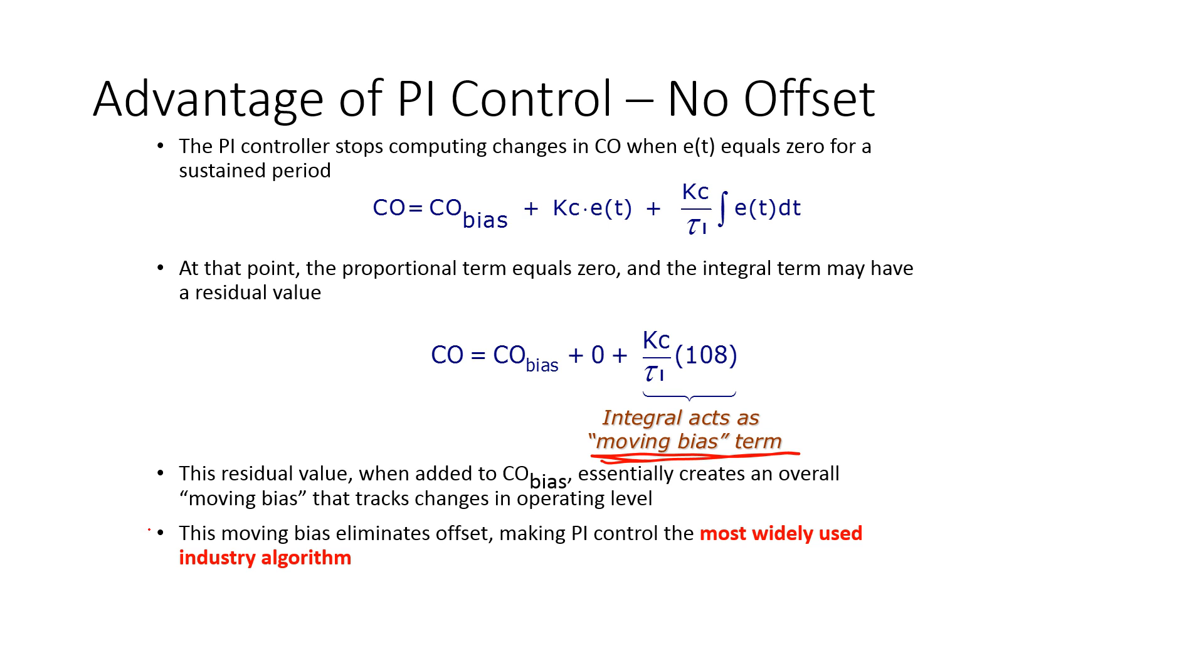One of the things to keep in mind, for PID controllers, the PI form is probably the most widely used in industry. Most people don't put a derivative term on there, only in special cases where you want to try to limit the amount of overshoot.